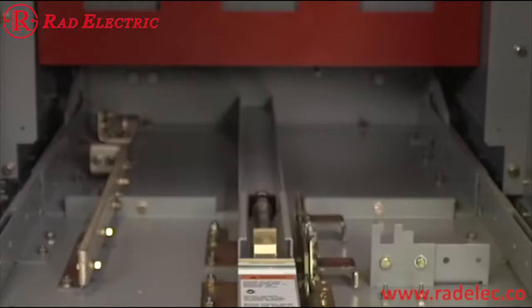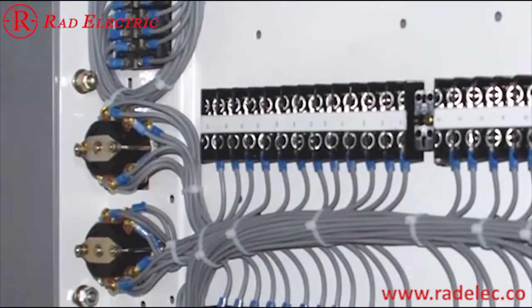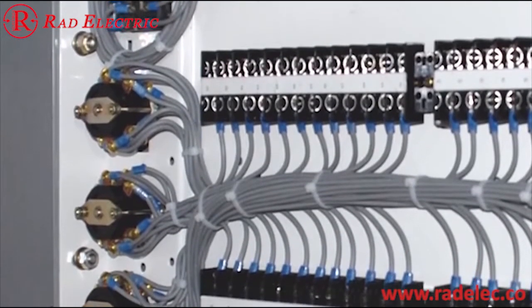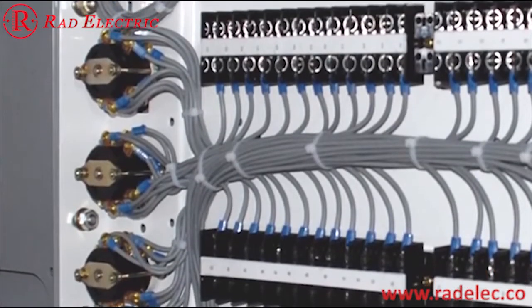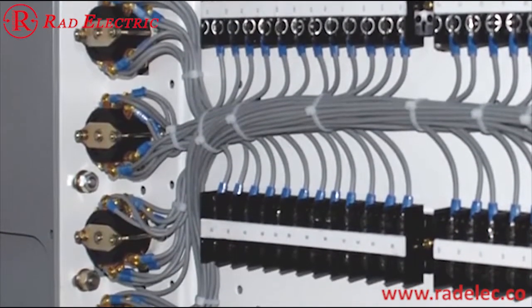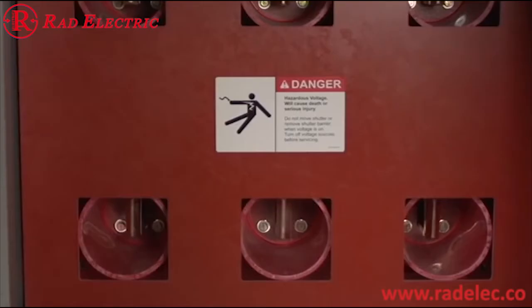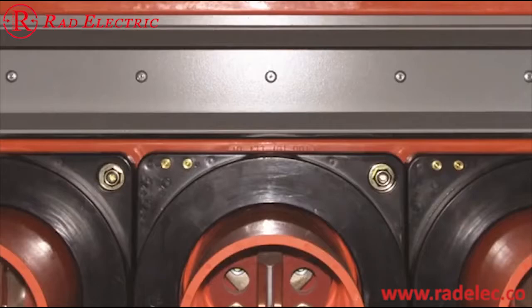Running along the right and left side of this section are passageways for wiring. They go through the bottom and up into the auxiliary compartment. On the right side of this cell are the MOC and TOC assemblies. These are used in the controls and protection schemes for medium voltage switchgear. When the shutter is open, you'll see exposed bushings and primary disconnect stabs. You can also see the black current transformers, which are optional, mounted on the bottom.